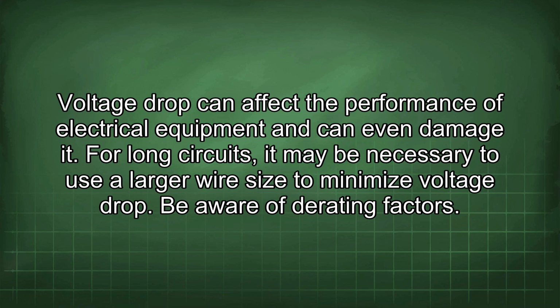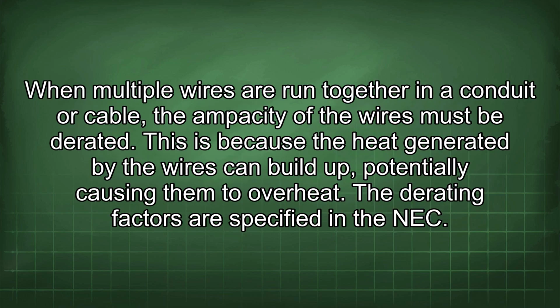Be aware of derating factors. When multiple wires are run together in a conduit or cable, the ampacity of the wires must be derated. This is because the heat generated by the wires can build up, potentially causing them to overheat. The derating factors are specified in the NEC.